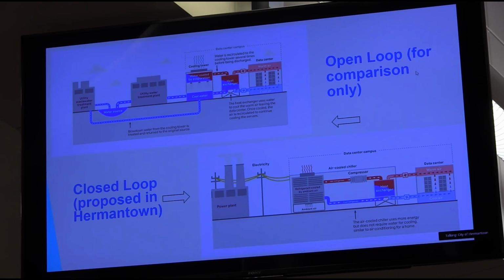Just a bit more on this diagram. The lower image is the closed loop system. There's an internal loop inside the data center going to a heat exchanger. The water in that closed loop is cooled and returned to cool the servers. The external loop, also closed, goes to either a dry cooler or an air cooler. There's a compressor, which can be bypassed, particularly with dry cooling technology. Outside air is used to cool that loop, which is returned via the heat exchanger to cool the data center.